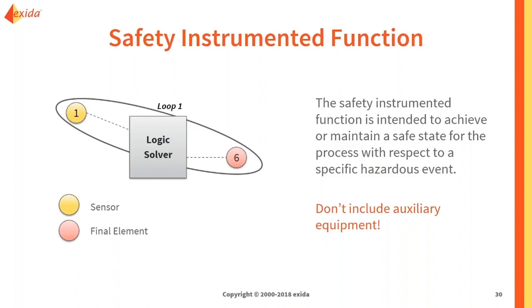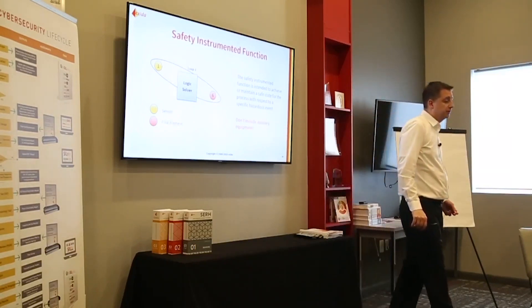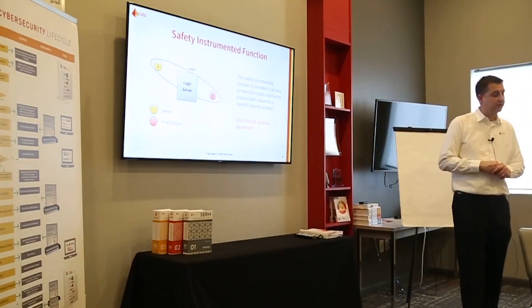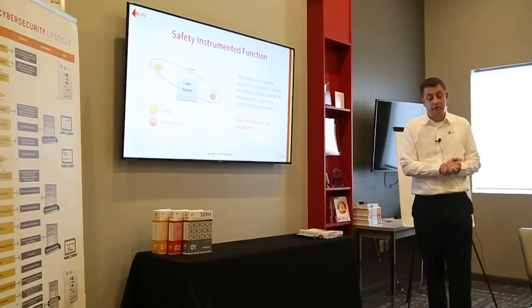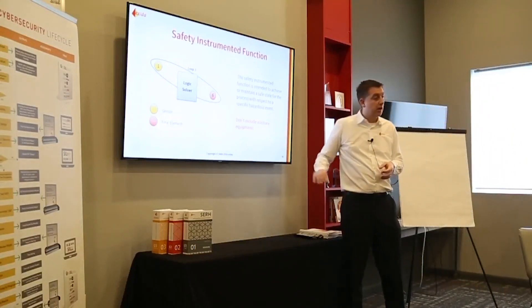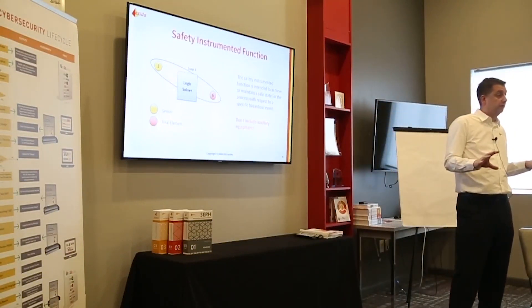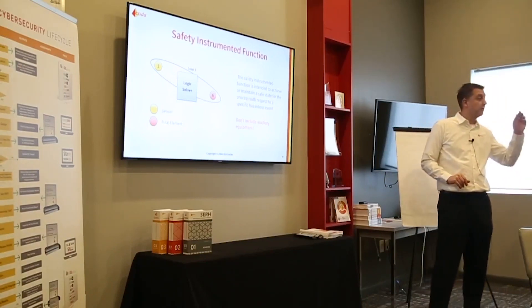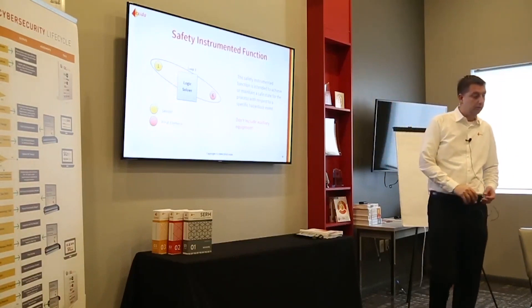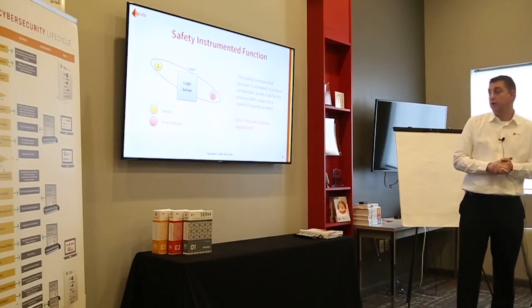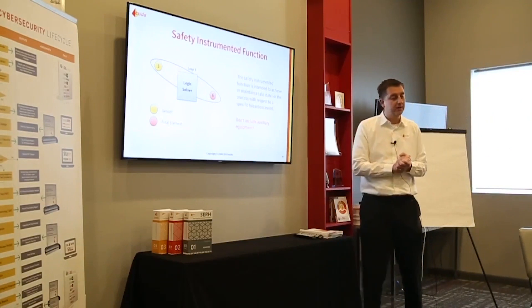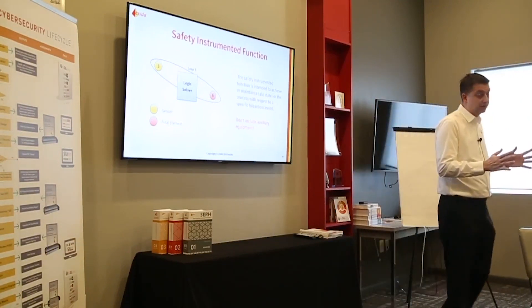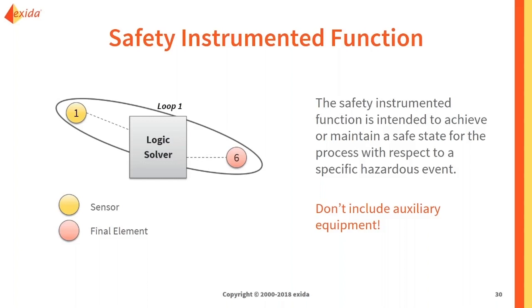For example, we detect pressure, and if pressure gets too high, we close an inlet valve. Sometimes there are extra activities we want to take once we try to achieve the safe state — such as sounding an alarm or shutting down an upstream process — but if those actions are not necessary to achieve the safe state, they are not part of our safety instrumented function. We always need to make sure we're not including auxiliary equipment.